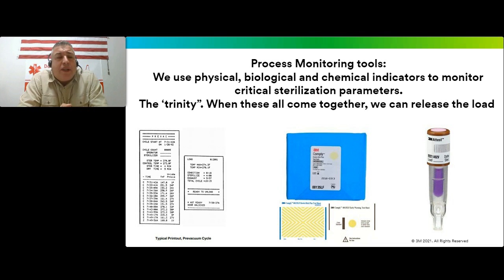On the left, you can see a printout from the sterilizer. We would look at that as a physical or mechanical device or monitor, making sure that the program settings—what we told the sterilizer to do—it's going to do. An important thing to know about these printouts is that they're going to tell you what you programmed the sterilizer to do.